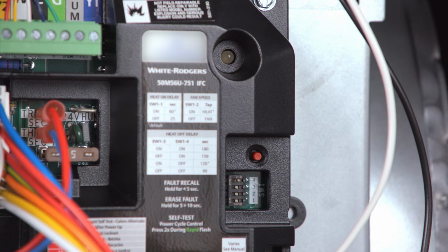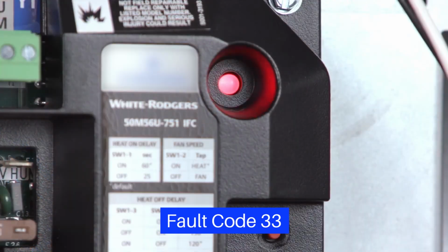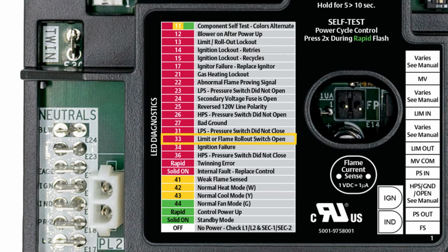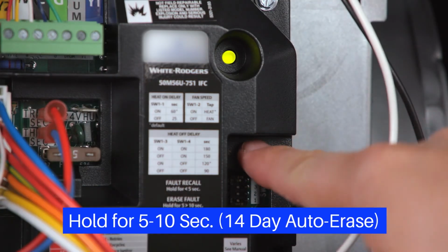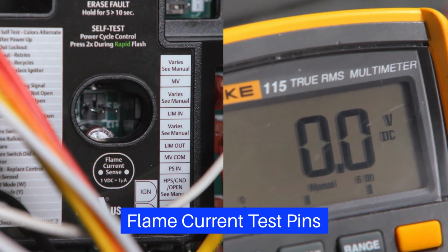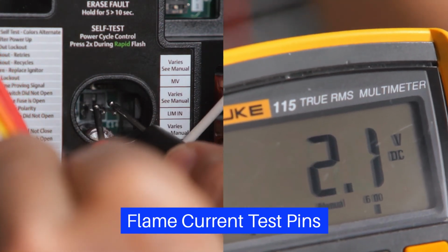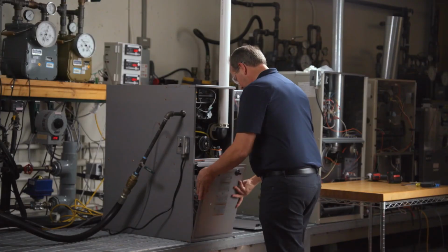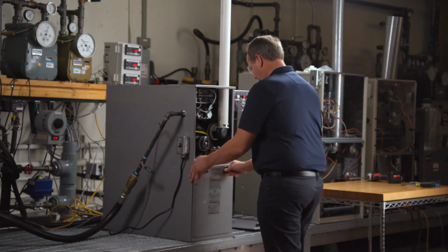If any faults occur during the cycle, a flash code will indicate the fault. The LED is displaying 3 short red flashes, followed by 3 long red flashes. The fault code label indicates a limit or flame rollout switch is open. To clear the fault codes, press the fault code button for 5 to 10 seconds. The flame current test pins are easy to access and provide the flame current reading. Reinstall any panels that were removed.